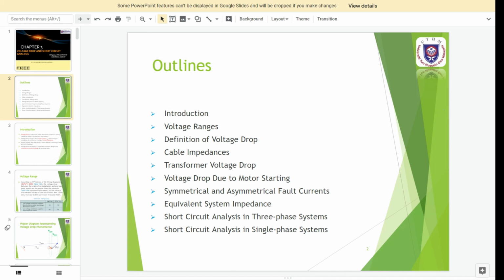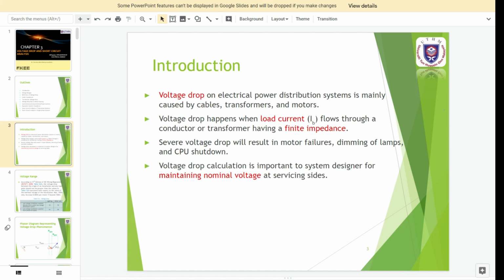And then more detail on the definition of voltage drop and cable impedances. We have to identify the voltage drop for the transformer and for motor starting, and then we will also include symmetrical and asymmetrical fault currents, the equivalent system impedance, and finally the short circuit analysis in three-phase and single-phase systems.